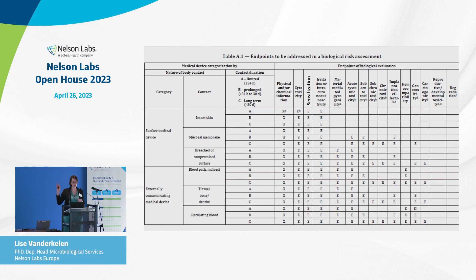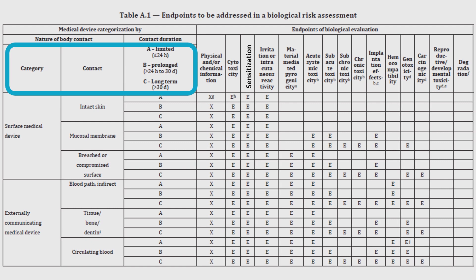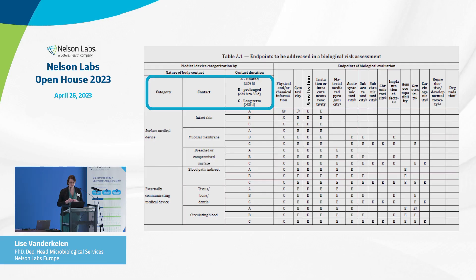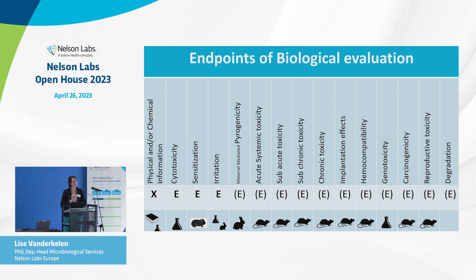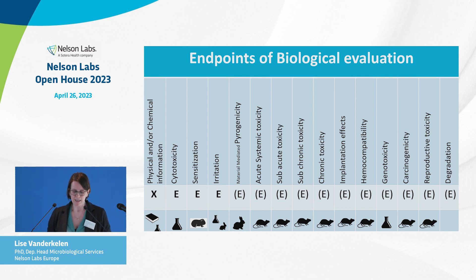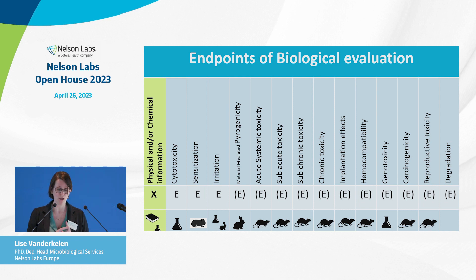I have projected the standard, Table A1, where you really see the categorization. Based on the category - just a part of the table for your information - you can see which endpoints you need to address. I've simplified the table into this simple slide, where you see all the endpoints you need to evaluate so that you can ultimately claim a biologically safe relationship. The E stands for evaluate - you need to evaluate, not necessarily test, every endpoint. When the E is in brackets, it means depending on the type of device, it's an endpoint to evaluate. For physical and chemical information, there stands an X, meaning this is a prerequisite to start your risk assessment. So you always start your first chapter with planning, with gathering as much information as possible.